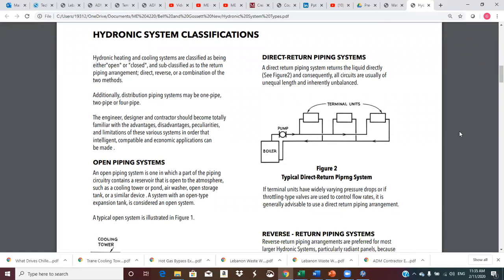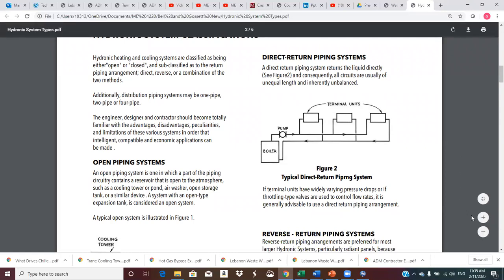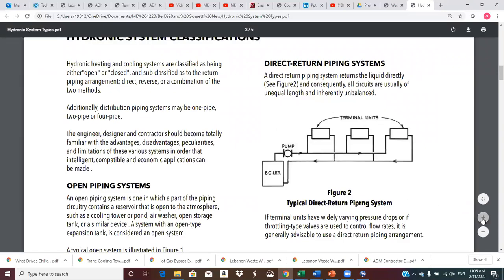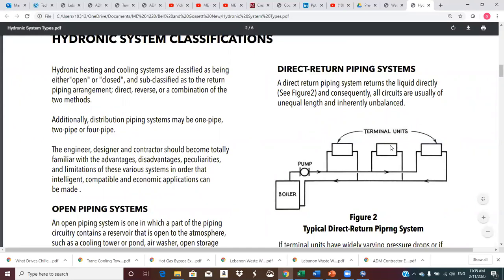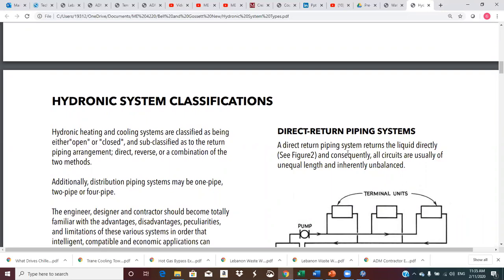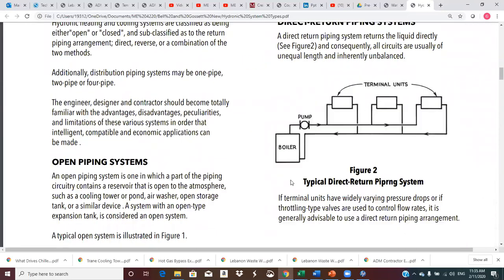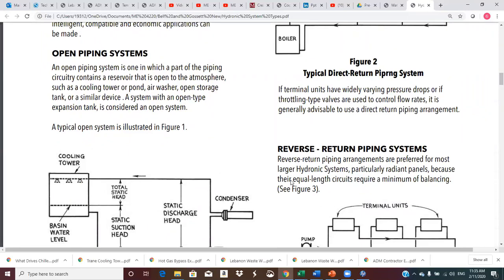So what we're looking at here is just some general classifications of hydronic systems. Let me make this one tab bigger, a little bit easier to see. Maybe two tabs bigger. There we go. So you can identify a hydronic system as either closed or open, and a piping arrangement as direct or reverse return, or can be a combination. So we're going to go through some of this. An open piping system is one in which part of the piping or circuitry contains a reservoir that's open, such as a cooling tower, and often there is an elevation change from where water is discharged from where it originates as it goes through this system.